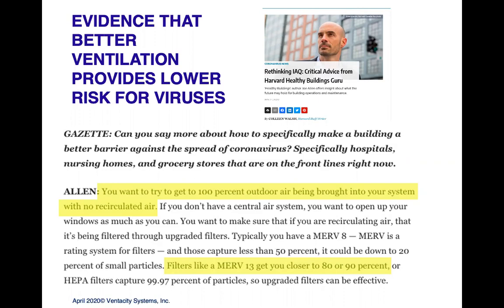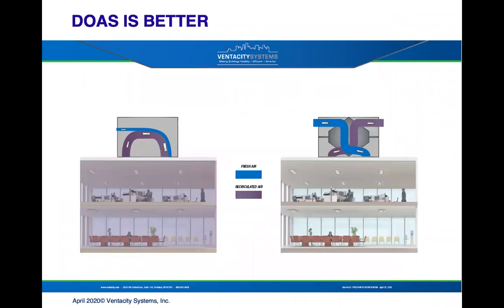With COVID-19 and viruses generally, we're not worried about what's outside, we're worried about what's inside more than that. But keeping high levels of filtration is important. Passive house requires MERV 13 filters. And this is the difference between, on the left, a rooftop unit that's recirculating, versus a dedicated outdoor air system with heat recovery, providing direct fresh, filtered air into the building. Exhaust air goes directly out, and as I mentioned, cross-wall contamination is nearly nil.